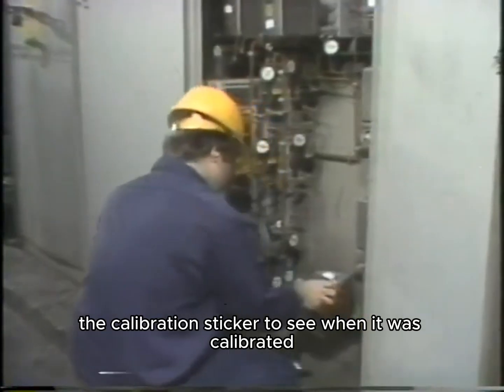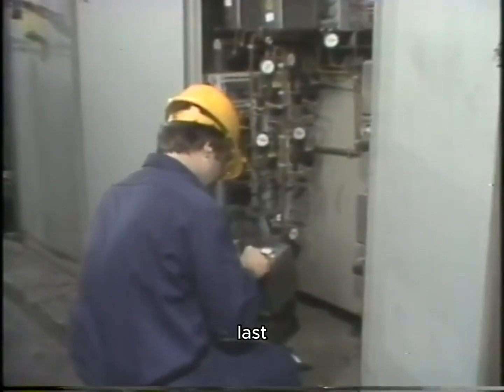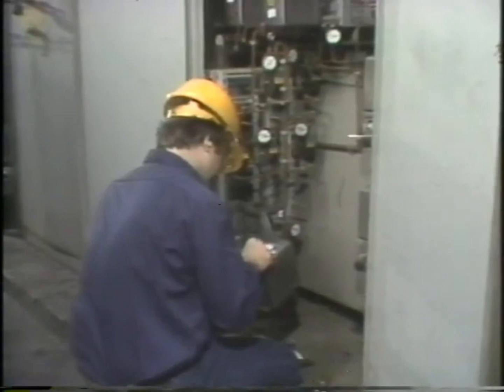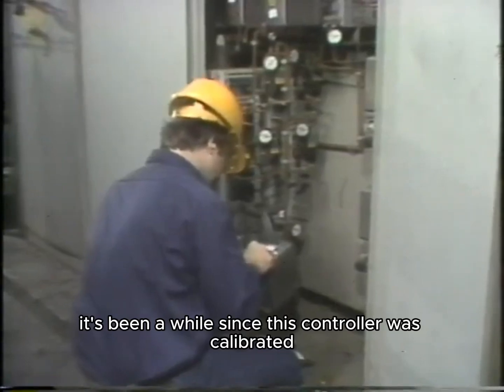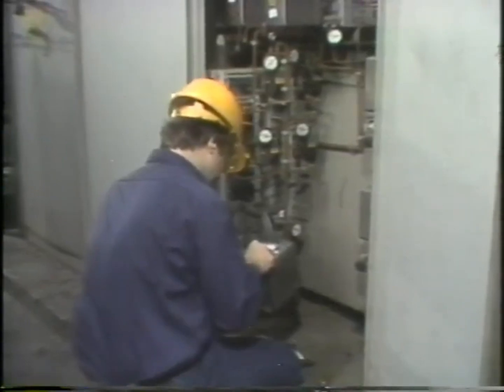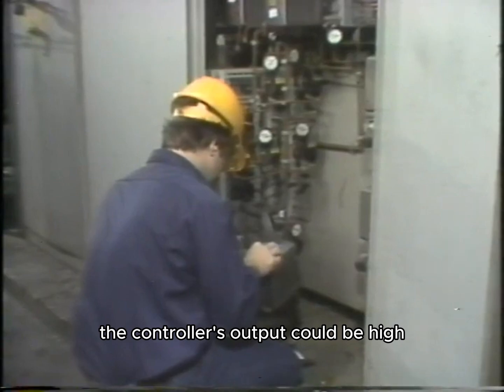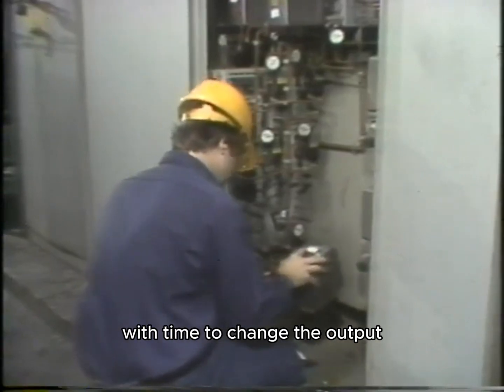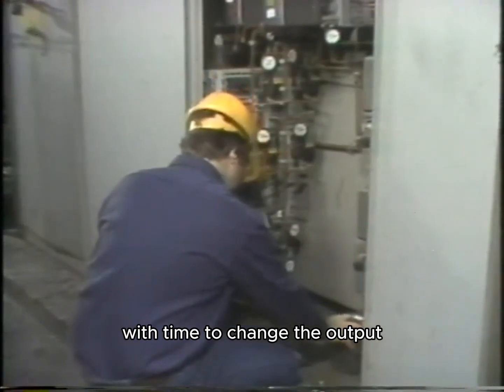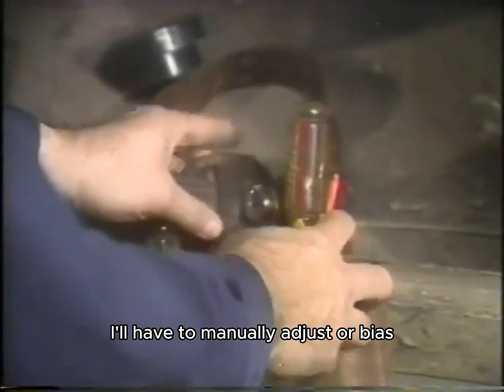I can check the calibration sticker to see when it was calibrated last. Oh yeah, it's been a while since this controller was calibrated. The controller's output could be high due to some calibration changes with time. To change the output, I'll have to manually adjust or bias the output of this controller.